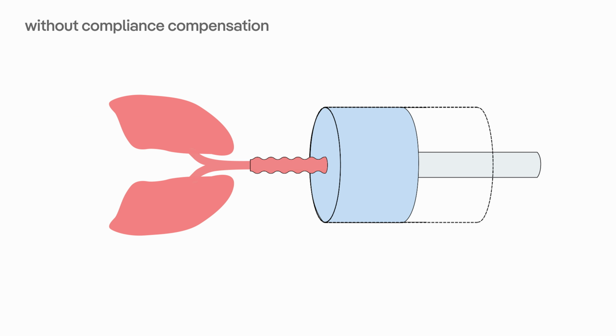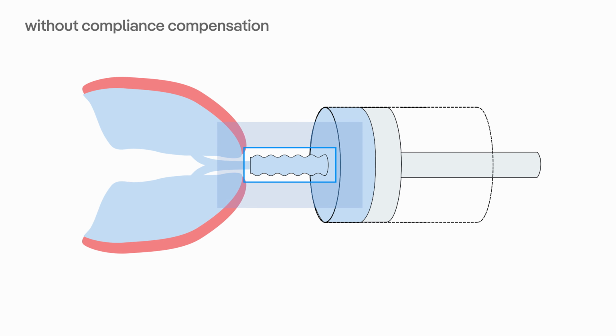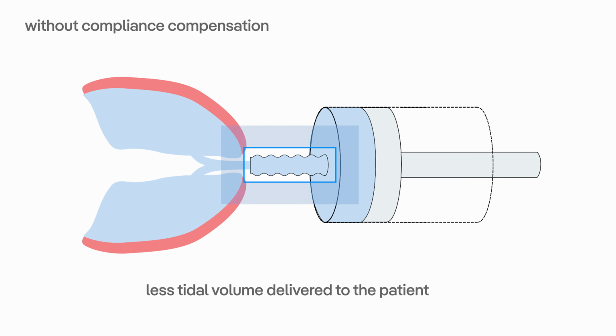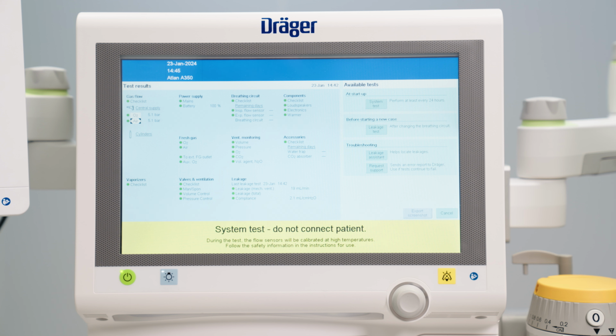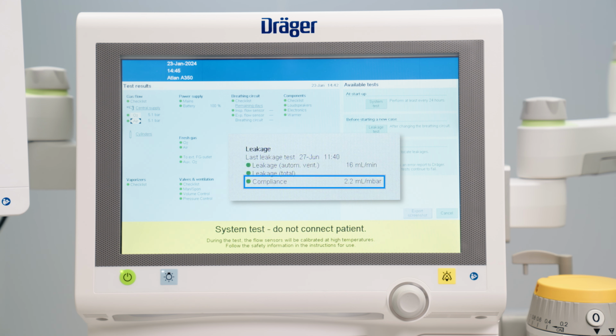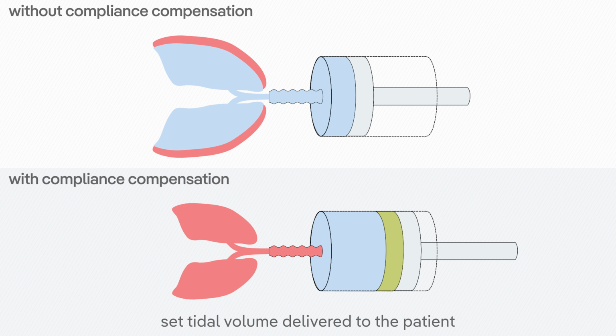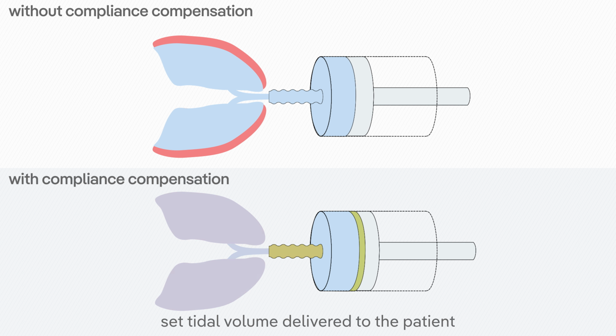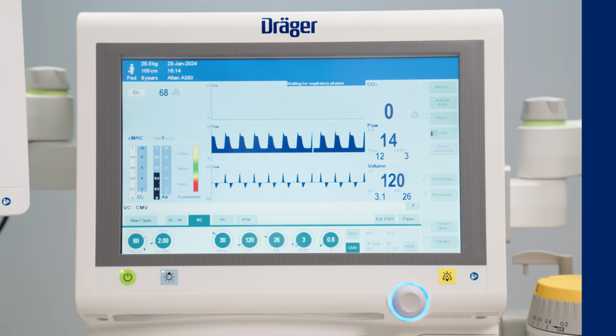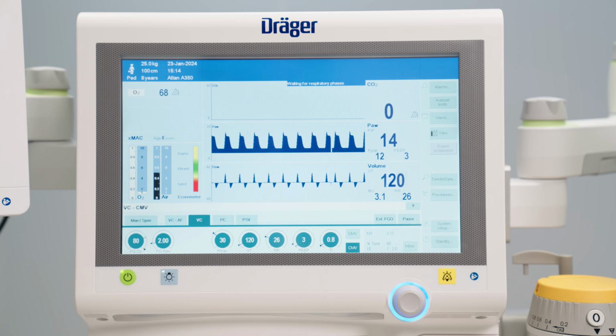Compliance refers to the fact that parts of the system volume of an anesthesia device, including the breathing hoses, can expand upon pressure. This causes them to take up volume, which should actually be delivered to the patient. Therefore, compliance has to be determined and compensated accordingly for accurate tidal volume delivery. Dräger anesthesia ventilators are able to compensate for the compliance of the breathing system and hoses, which is determined during the self-test. According to the compliance, the needed additional volume is calculated and compensated to deliver the exact tidal volume for each breath.